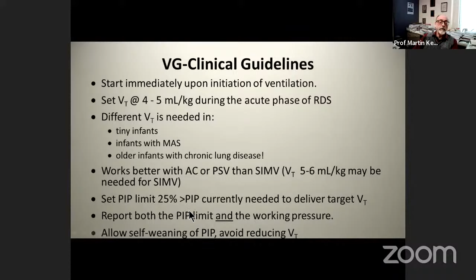But you may need a slightly larger tidal volume, because SIMV by itself without pressure support will need a bit larger tidal volume. And of course, we want to use the pressure limit as our safety alert if compliance is changed in a bad way and deteriorated and more pressure is needed. You want to know about it. And so keeping the pressure limit fairly close to your current working pressures gives you that information. And of course, we need to pay attention to what the baby's actually receiving, not just the pressure limit. And of course, we'll talk about weaning.